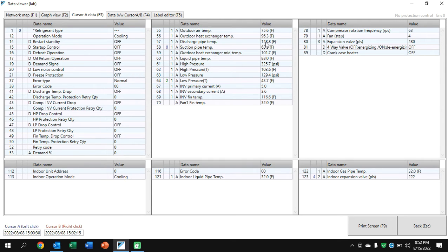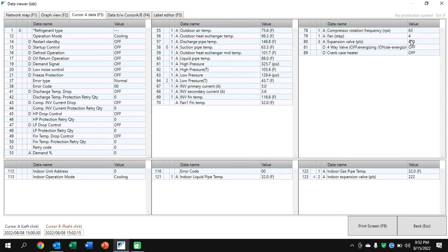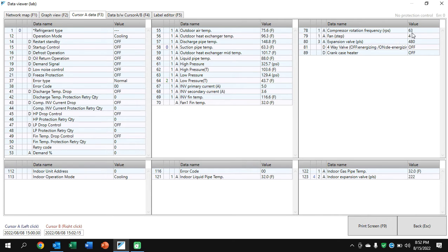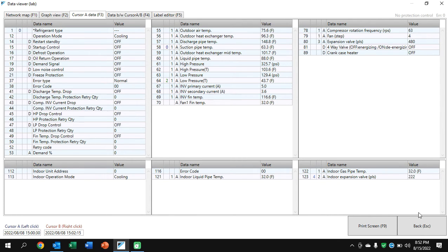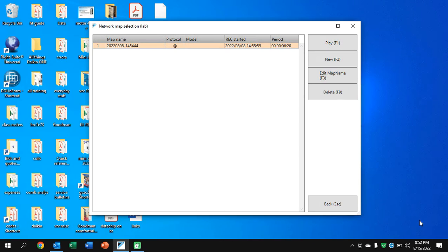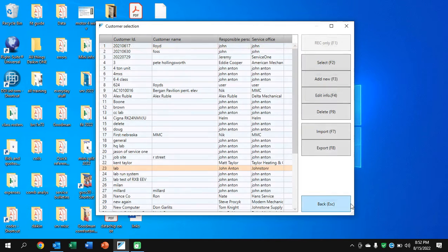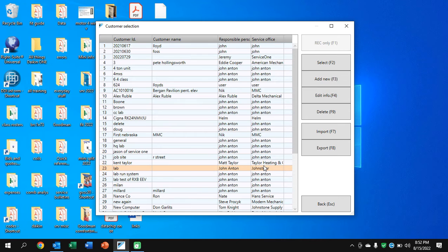We will have a troubleshooting portion just on the fit. But the rest of the data you can see here, use your common sense and troubleshooting discharge of the compressor. You know, when you're low on charge, you know what happens to the discharge. And you can monitor the different items for here. This allows you to measure every sensor, every pressure, all at one time and have it in front of you to see approximately what's going on. It'll also show you protection modes on the left if you're in a startup control or oil return.